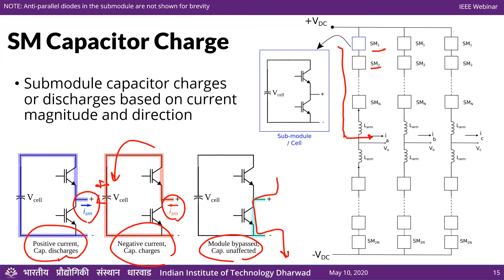A quick point to note: when the module is on, the controller has no choice over whether this capacitor will charge or discharge. Based on the current direction, it will either charge or discharge, and we cannot choose between these two. The only thing we can choose is whether it's affected or stays unaffected, and to do that, the module is simply bypassed.